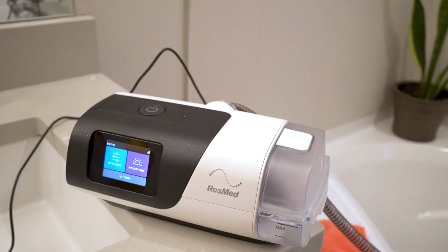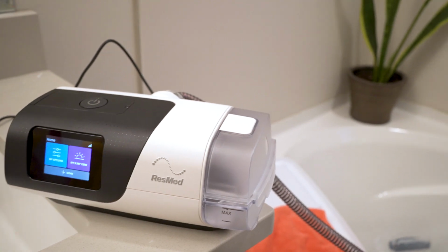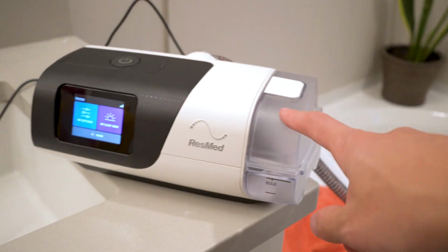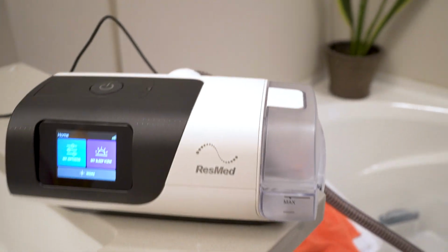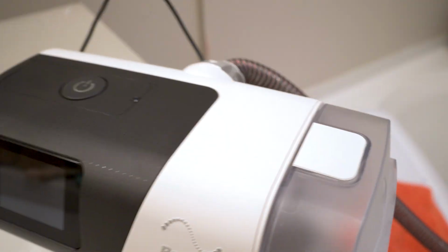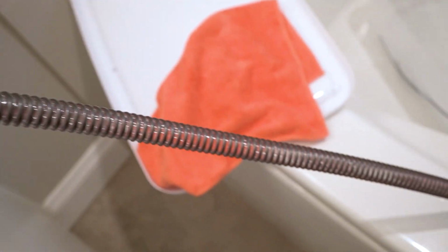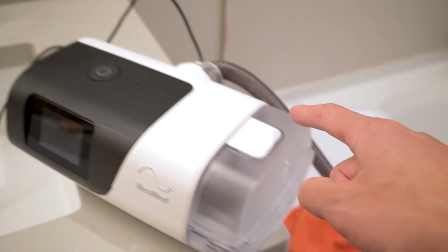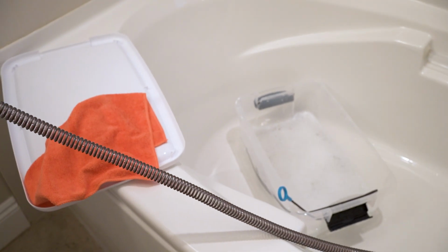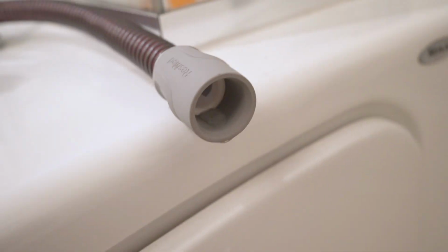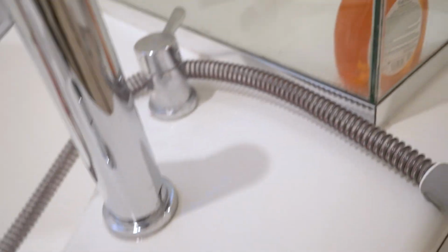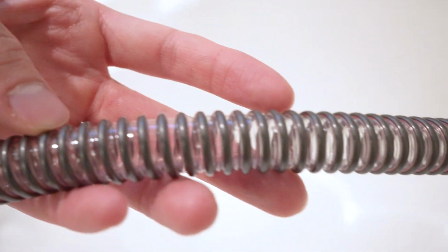Okay, so I have the tube connected to my machine. You'd obviously want to be doing this in your bedroom, but for simplicity's sake, we're just doing it in the bathroom. And we have no water in the humidification chamber, so we're just going to go and turn it on, okay? As you can see now, the CPAP is drying the tube here. And it's always best to have the tube going down with gravity so it dries the fastest possible. You can even see the tube here. You can see the water already blowing out of the tube. You see the water droplets kind of going down. So it doesn't take very long at all for the water to come out of the tube. It's already looking pretty dry.